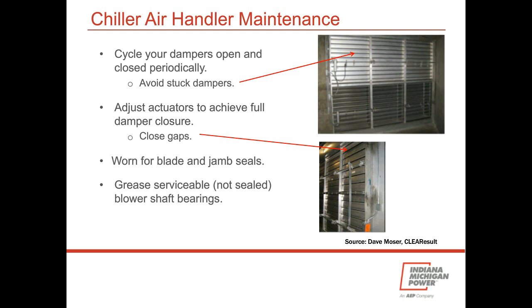This requires one person at the control system workstation and another person actually observing a damper operation. I have a good friend who used to work with one of the major HVAC maintenance companies, and he said it was very common for his staff, the maintenance techs like himself, to just look at the workstation and the computer sensors and trust that they were reliably indicative of what's actually going on outside. He himself would ask the dampers to be open, walk outside, and check to see that they are. You can see here on the right-hand side, half of them open, and half of them did not.